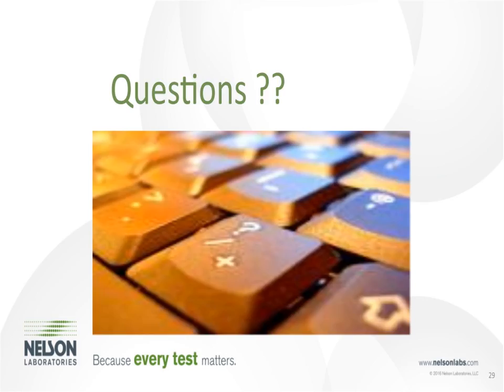For example, irritation was updated in 2010 to where it went from a 2-rabbit to a 3-rabbit test, and it also changed how the scoring criteria was done. So an evaluation can be done to see if we can still use those results. Even if you used a 2-rabbit test, we still may be able to evaluate the results and make an assessment that a third rabbit would not change the impact.